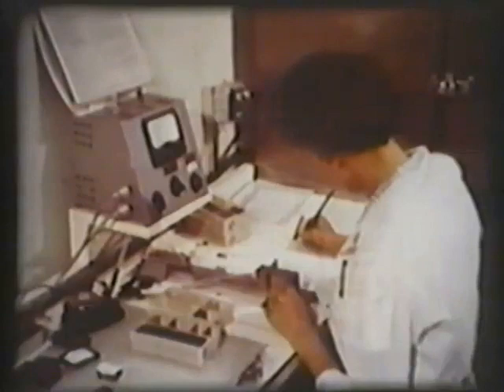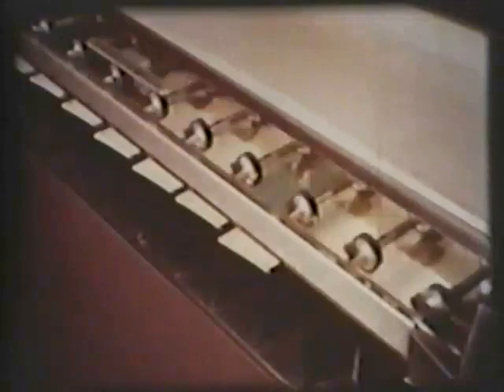Within 3 hours after each entry into the SL-1 site, film badges were processed to determine the precise exposures received. After the initial entry, no personnel received more than 9 roentgens gamma exposure. Special data processing procedures had been initiated by January 4th, involving 2 or more film badges daily for many individuals. Total radiation exposure was tabulated on summary cards.